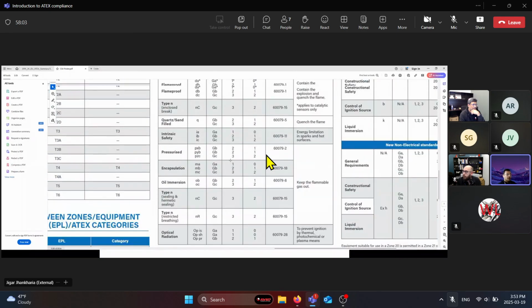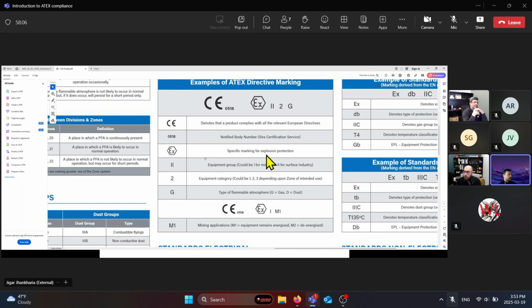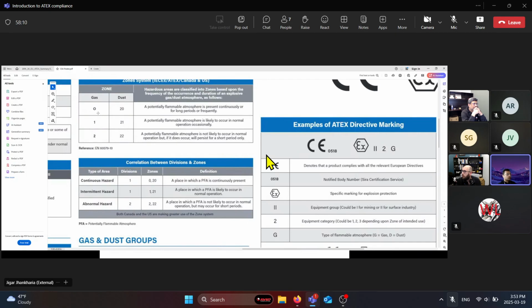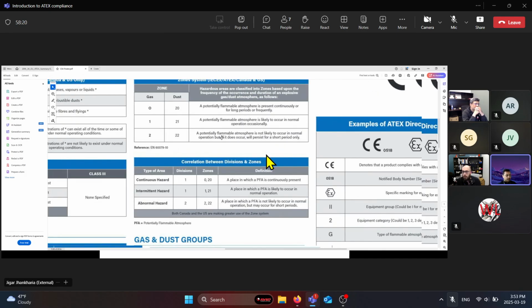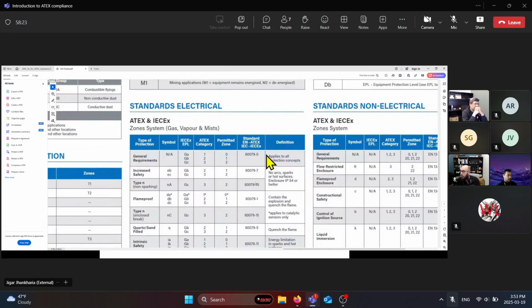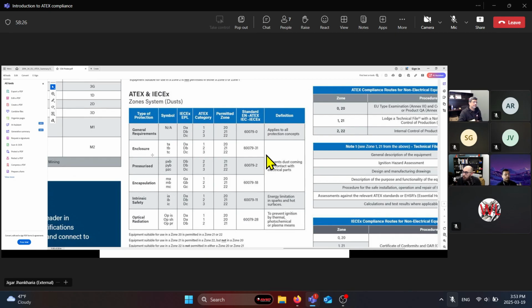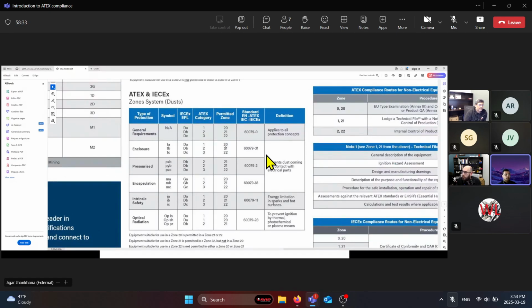Classification of zone 20, 21, 22 is pretty much the same here. You can see it's the same as 0, 1, 2 in terms of the concentrations of dust in each environment, but there is only very specific standards that are applicable to dust. So one is enclosure protection, which is 79-31. It can be certified for zone 20, 21, or 22. This usually applies to any product that has like an electrical panel that can be certified to TB, TA, or TC method of protection, to prevent dust coming into contact with the electrical parts.